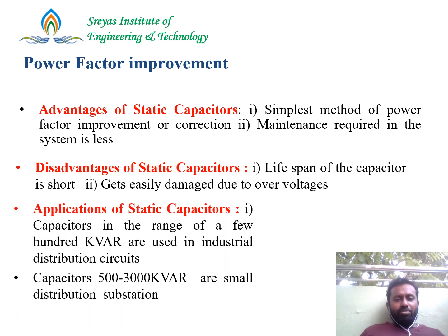Now, applications of static capacitors. Capacitors in the range of a few hundred kilovolt ampere reactive are used in industrial distribution circuits. Capacitors of 500 to 3000 kVAR are used in small distributions.